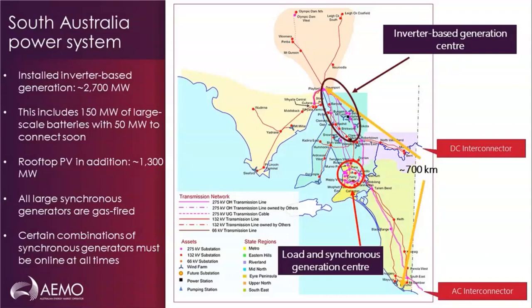What it means is that islanding or separation of this system has occurred frequently over the past 20 plus years that this system has been interconnected. We maintain a certain quantity and combination of synchronous generators in our South Australian system, and indeed all five eastern systems that we operate, to maintain sufficient levels of system strength and inertia. So these are effectively 24/7 requirements.